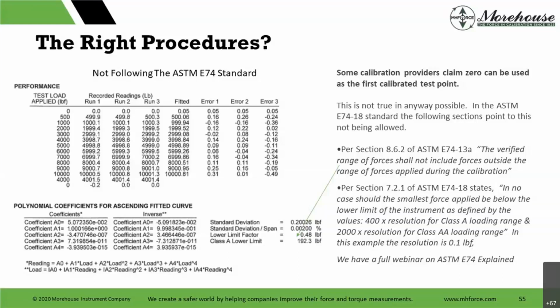This customer right here assigned a verified range of forces, Class A lower limit of 192.3 pounds, where the sections of the standards are quite clear in 7.2.1 and 8.6 that this certificate should have said 500, because that's the first non-zero force point. So know what you're getting, understand what your calibration provider is doing, try to check it.